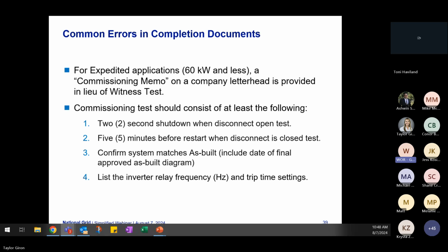For our expedited projects that are less than 60 kW, a commissioning memo is used. So most of the time, we will take a commissioning memo in lieu of a witness test. The commissioning memo should have the 2-second shutdown when disconnect is open test, as well as the 5-minute wait before restart when disconnect is closed test. Confirm that the system matches the as-built and include the final date of the approved as-built on the memo. List the inverter relay frequency and trip time settings on our commissioning memo.